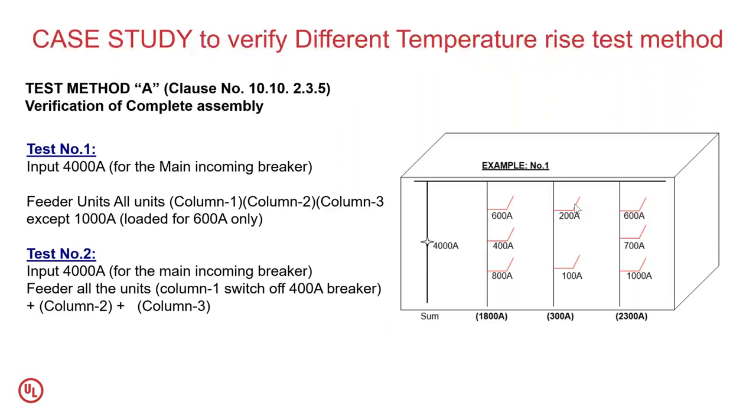Here is the first test of what I will do. I will pass the current in column 1, column 2, column 3, where I will only pass 600 amps in the 1000 amps feeder to ensure total 4000 amperes flows through the feeders of the switchboard. Because the 1000 amps feeder is not tested fully for its 1000 amperes rating, I go with a second test, means two tests are going to happen here. Same again, input 4000 amperes. Again, column 1, column 2, column 3. Now what I will do, in column 1, the 400 amperes breaker, I'll switch off so that the 1000 amps feeder is fully loaded. Again, the total sum, if I switch off the 400 amperes feeder, total current again flows 4000 amperes, so that by test number 1 and test number 2, all the breakers, all the feeders are tested with rated current declared by the manufacturer.